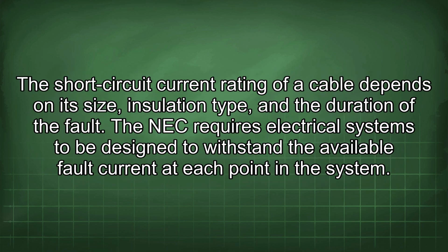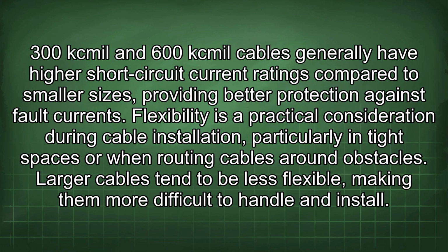The short-circuit current rating of a cable depends on its size, insulation type, and the duration of the fault. The NEC requires electrical systems to be designed to withstand the available fault current at each point in the system. 300kcmil and 600kcmil cables generally have higher short-circuit current ratings compared to smaller sizes, providing better protection against fault currents.